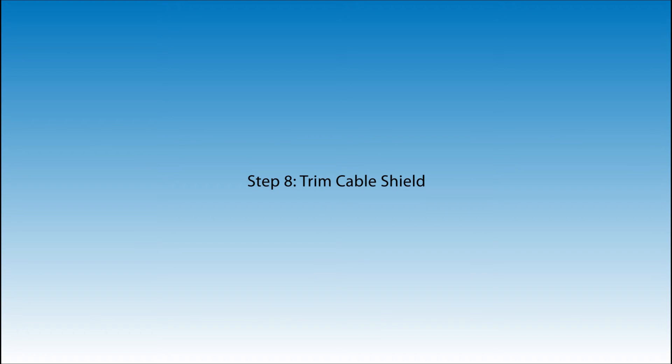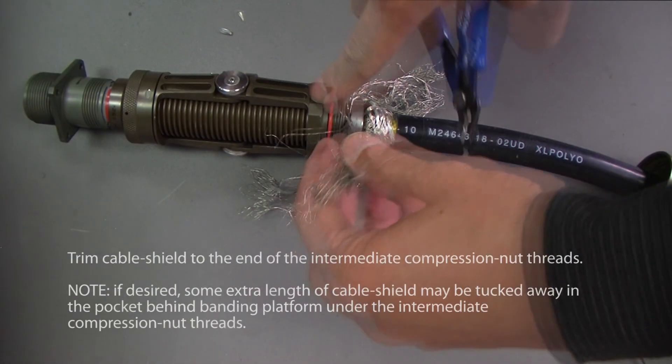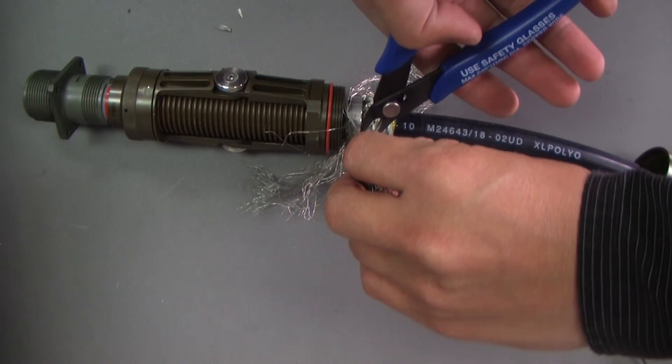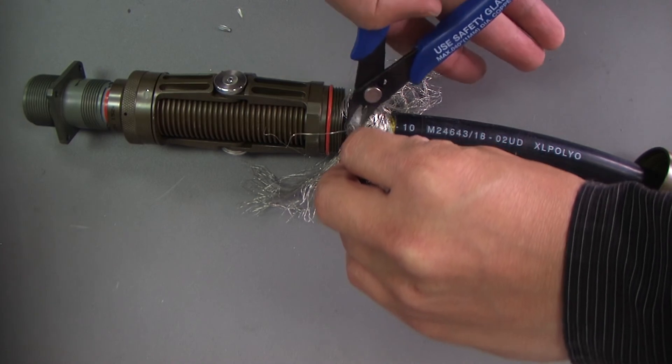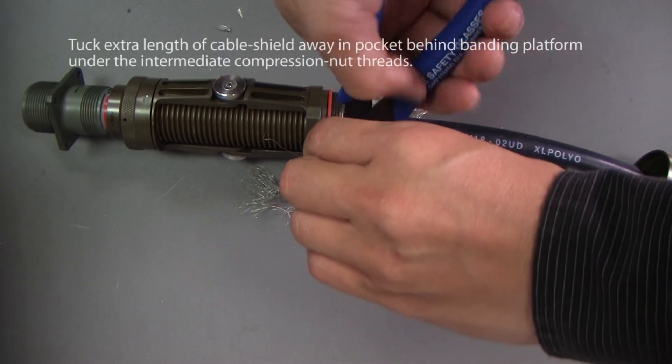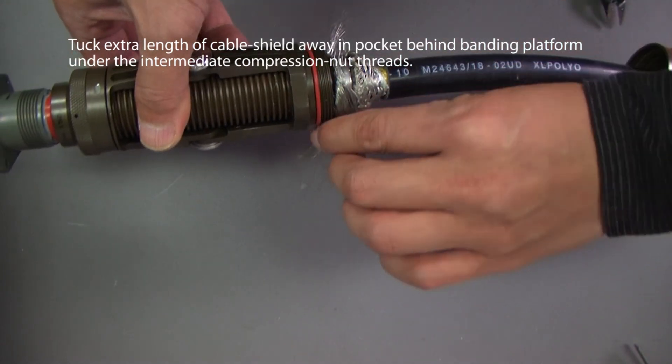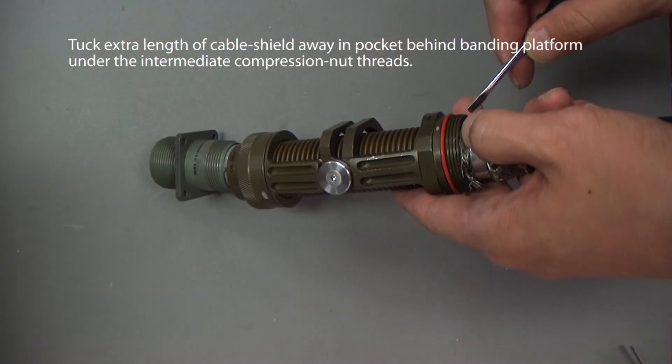This procedure ensures that Kevlar strength members are preloaded and adequate fiber slack is provided inside the back shell. Step 8: Trim cable shield. Trim the cable shield to the end of the intermediate compression nut threads. Tuck extra length of cable shield away in pocket behind banding platform under the intermediate compression nut threads.